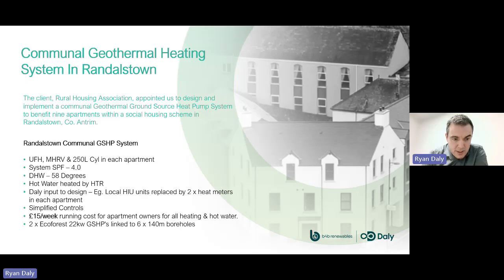Hot water is heated a lot by the HTR function in the heat pump that I mentioned earlier. And we had a good bit of input in the design, so there was an M&E consultant on it. We worked closely with them. They actually had HIU heat interface units on the scheme, and we proposed to replace them with just two simple heat meters, because we were worried about losing 4 to 5 degrees delta across that plate heat exchanger with the heat interface units. Plus, it didn't really need it. I didn't see any other justification for having them.